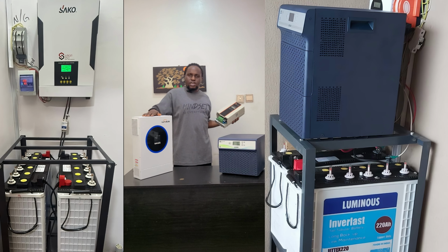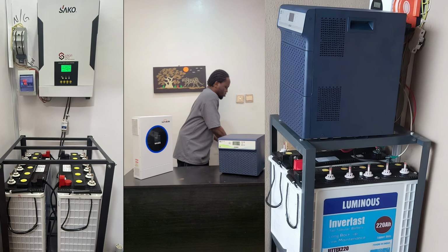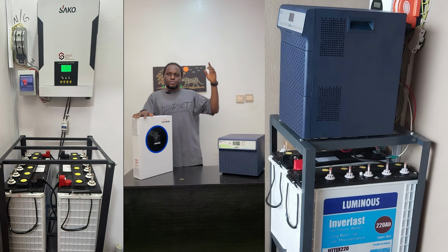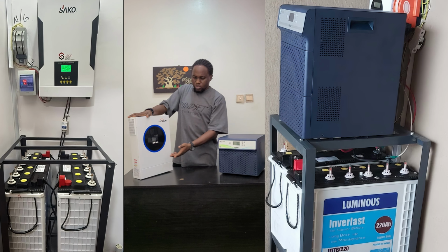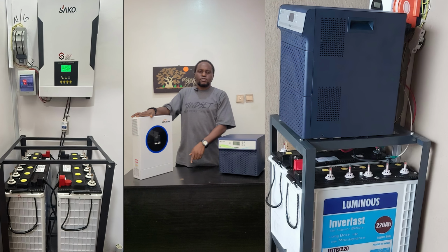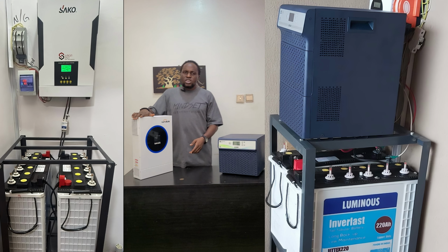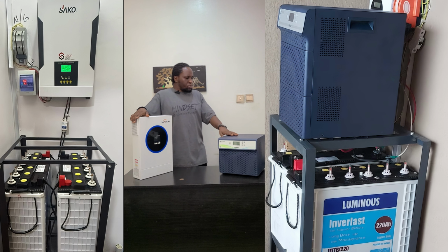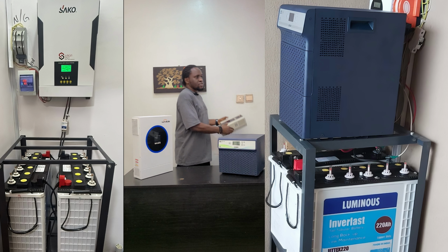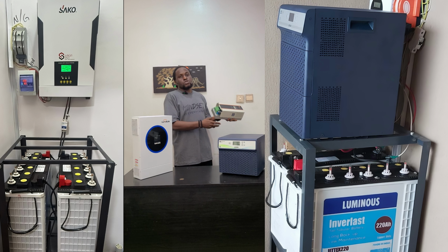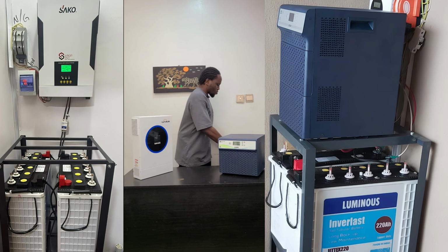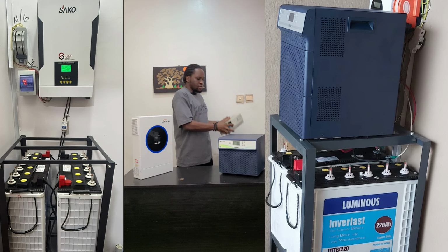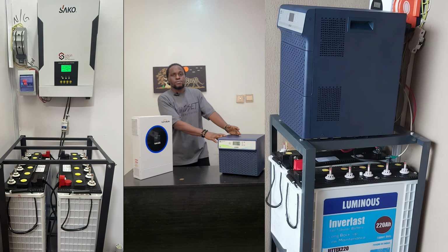But this is inside this inverter, so you're actually feeding in the solar panels to this, and also connecting the batteries to it. So if there is a fault in the solar charging system, normally for this guy, we'll just take this out if it can be repaired or if it needs to be changed. But while this one is out, this inverter is still working.